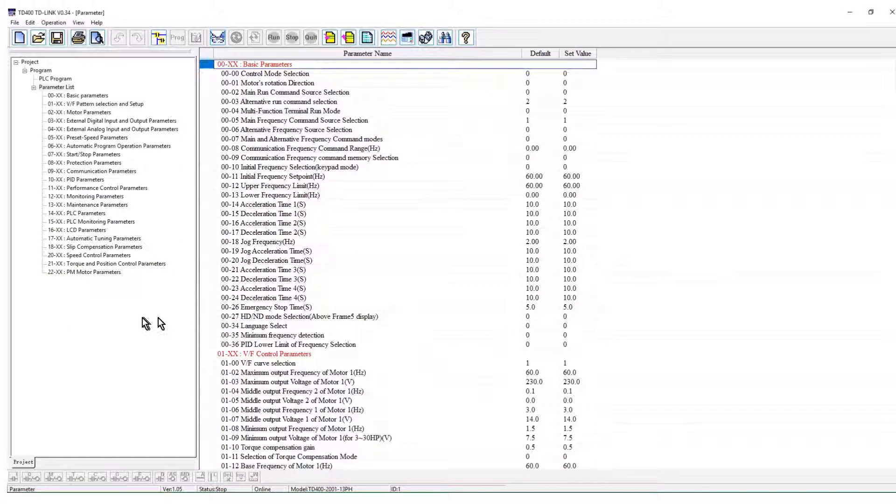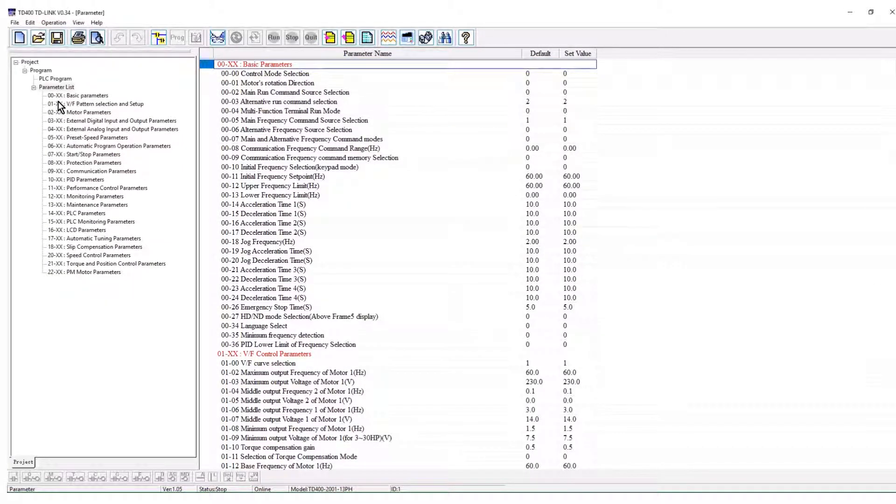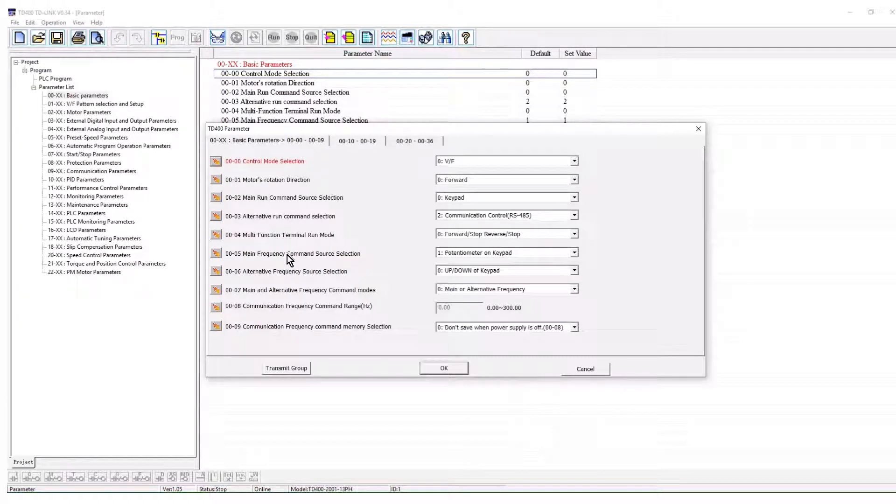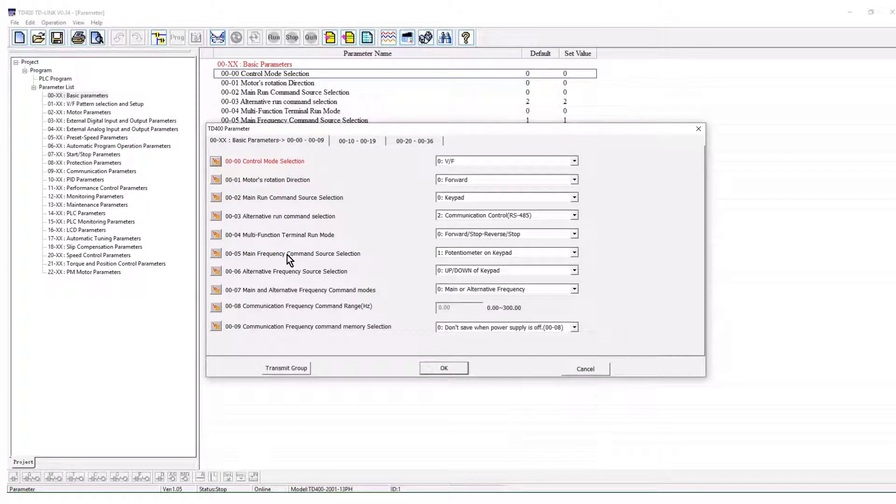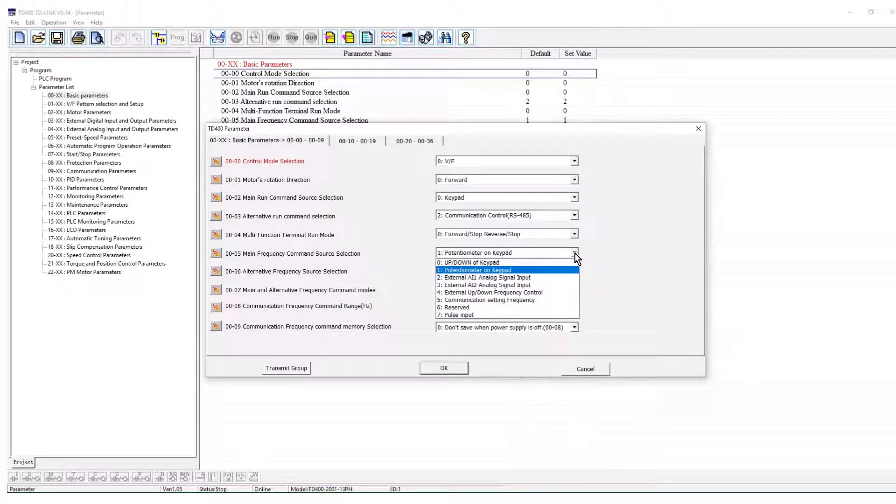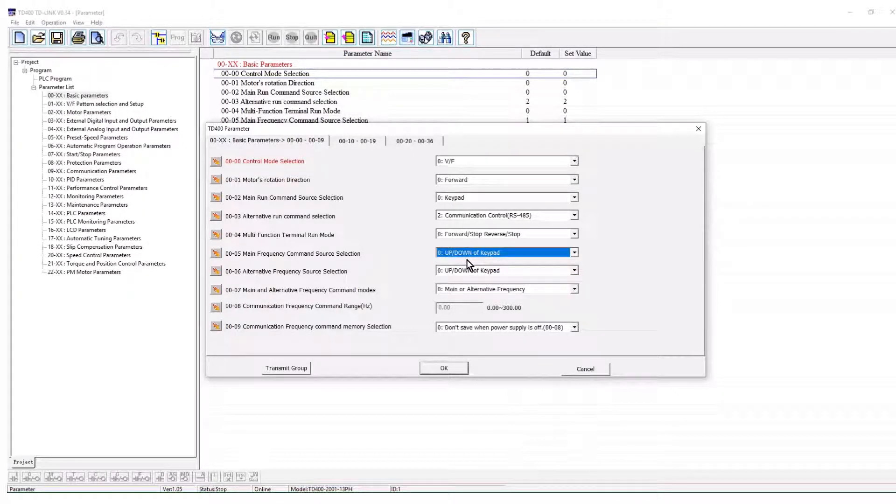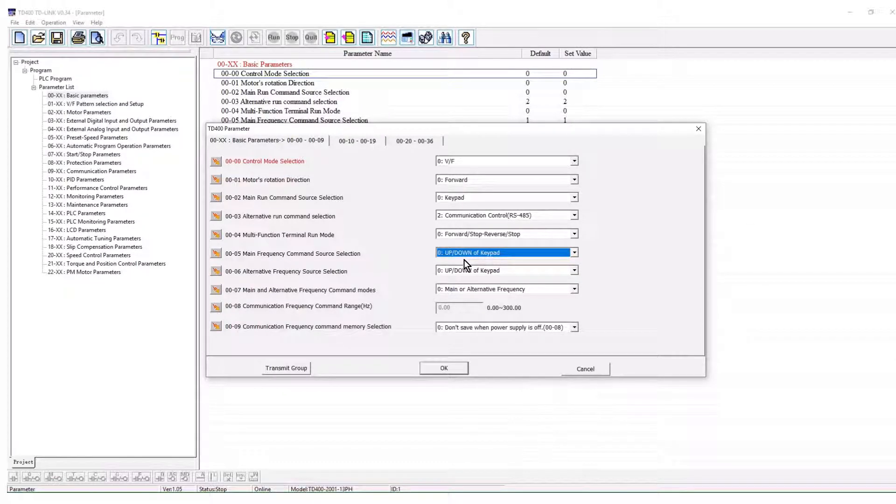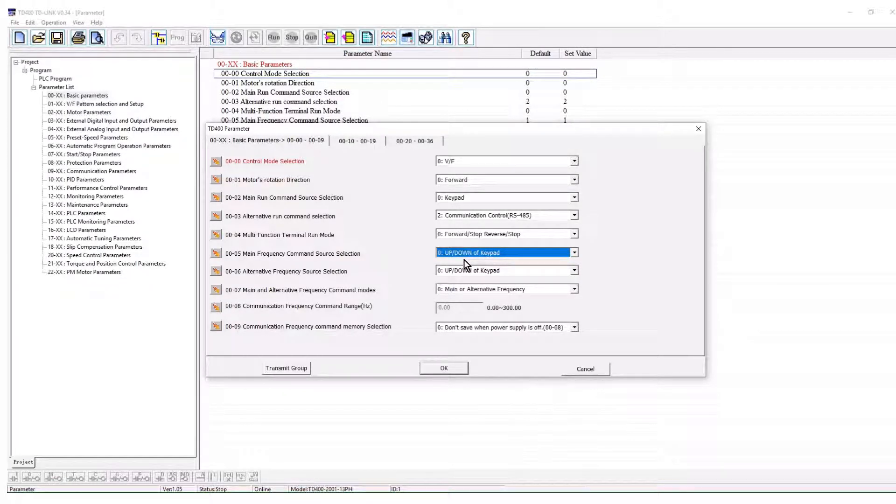Parameter group 0 will open initially. By default, the frequency command adjust is a value of 1 for the keypad potentiometer. We will change to a value of 0 by clicking on the selection. The main frequency command is now the up-down arrows on the keypad.